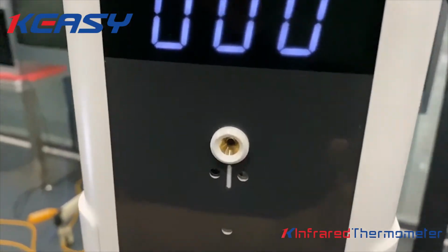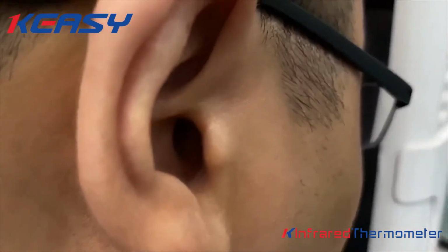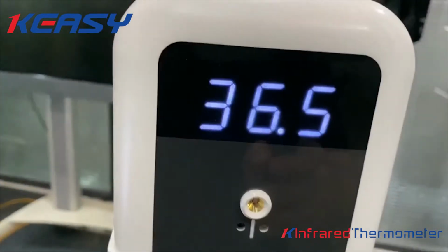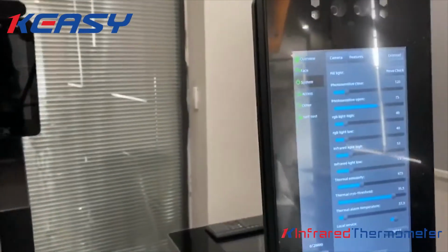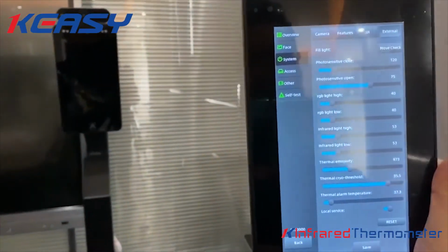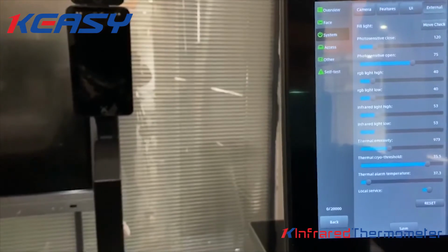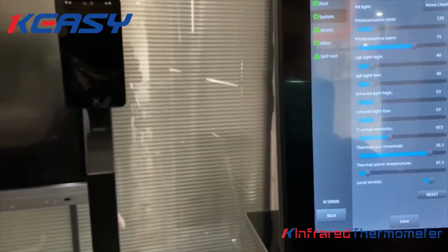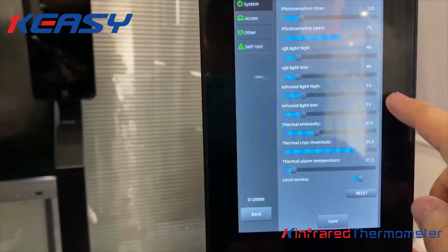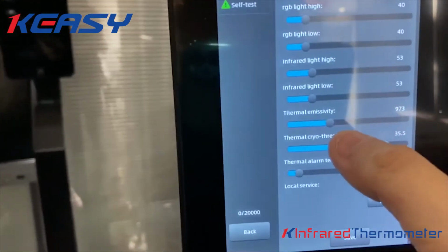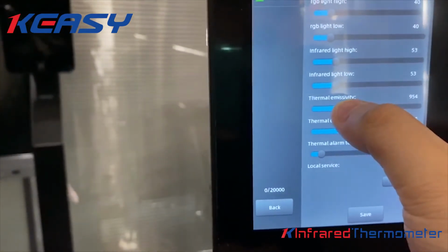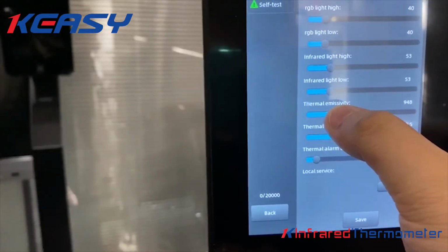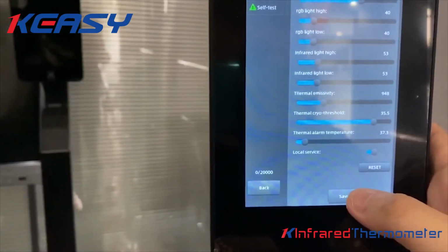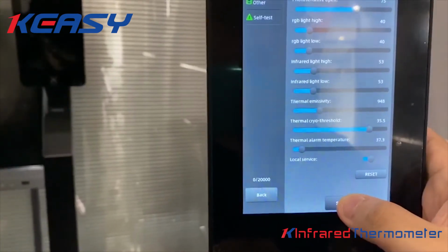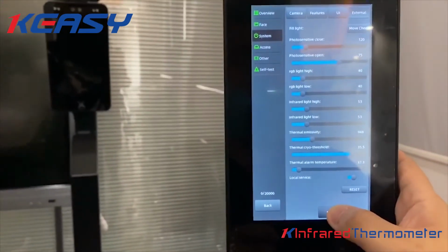Just before, now we go back to test my temperature again. 36.5. But a minute ago, my temperature was 32 here. So if the temperature here is lower than the thermometer, we have to set this value lower. Maybe now we set it to 948 and save. After power on again, we will need to test the temperature once again.